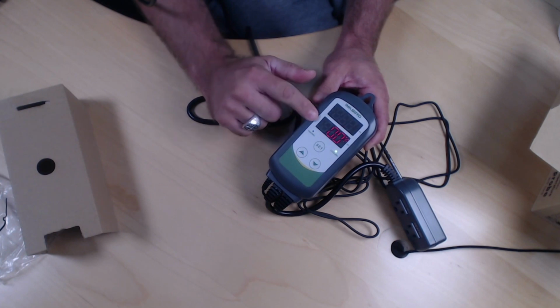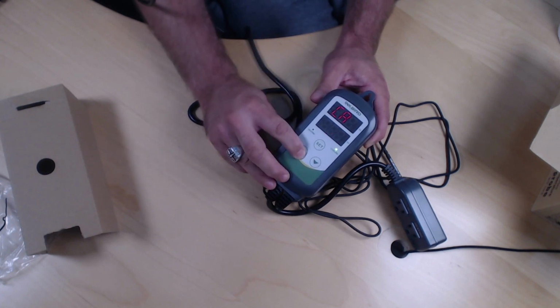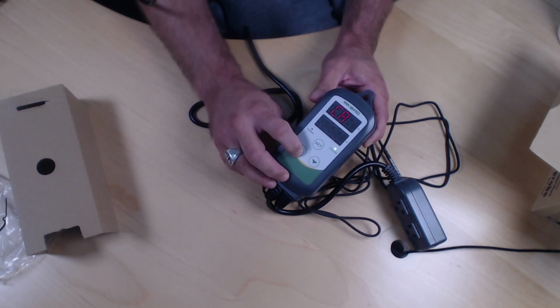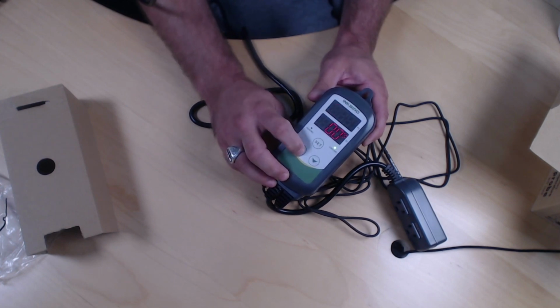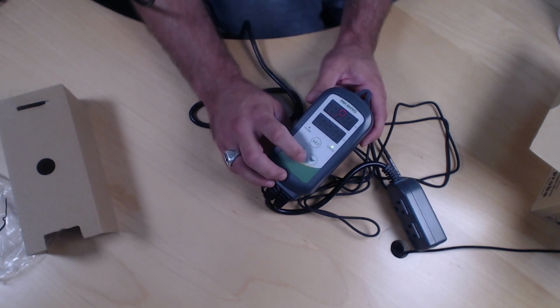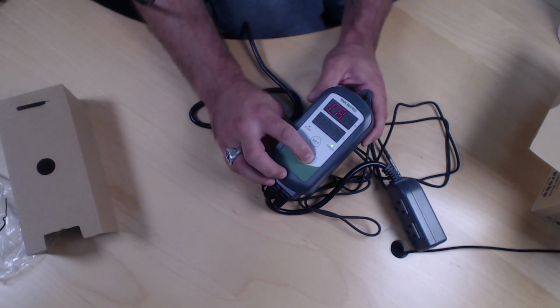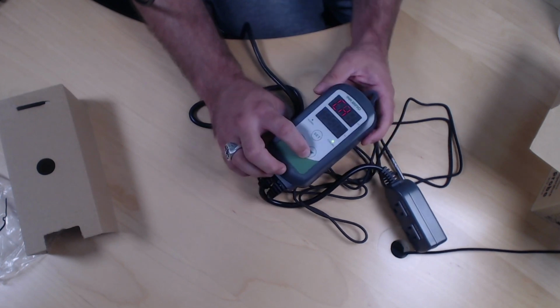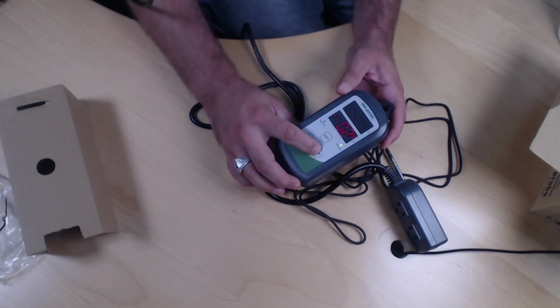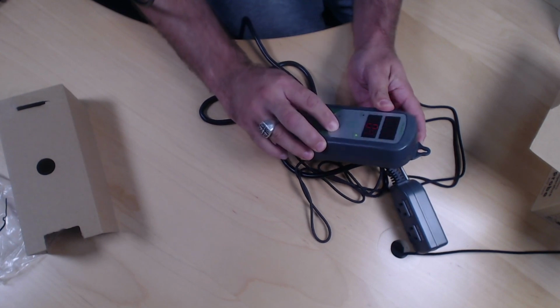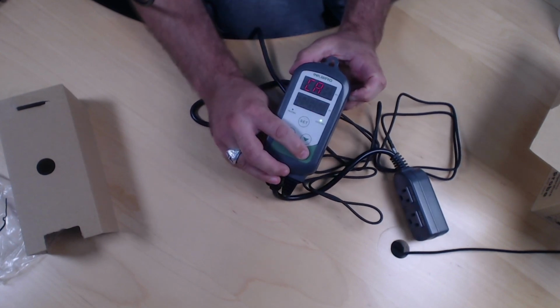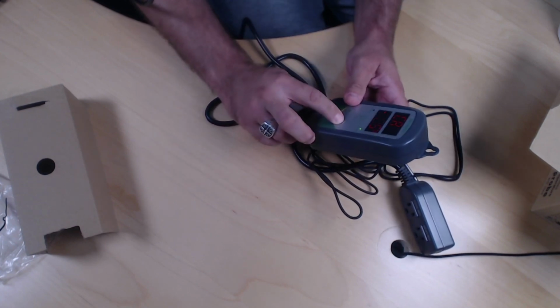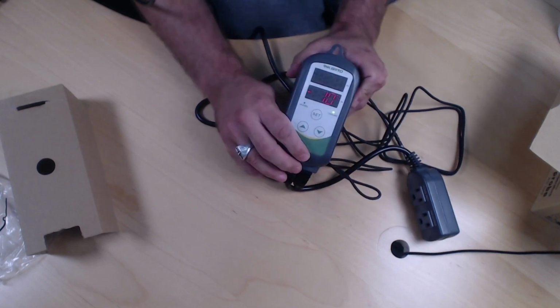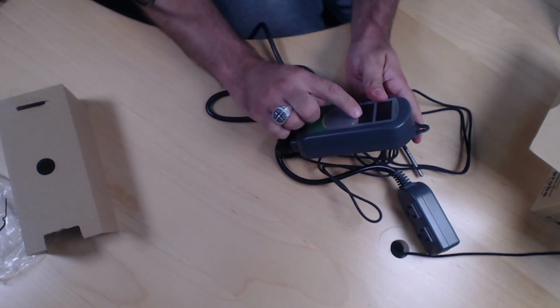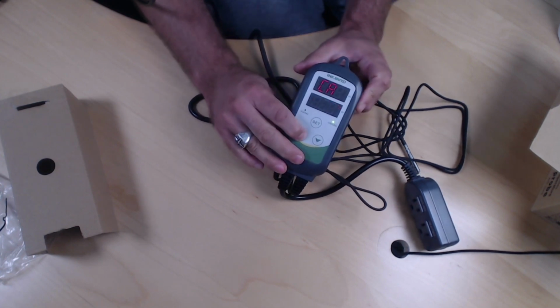This is the calibration. If your probe is saying it's 70 but really it's 68 because you have some other calibrated analog thermometer that you trust, you can do an offset on here to compensate for the degrees you're off, and it is in fractions. So that's not 4 degrees lower, that's 0.4 degrees lower. If I keep going, now I'm at 1 degree. Make sure you understand there's a tiny decimal in there if you're setting an offset.